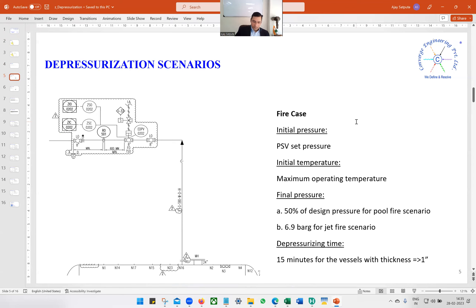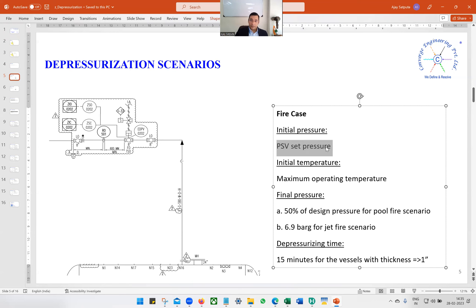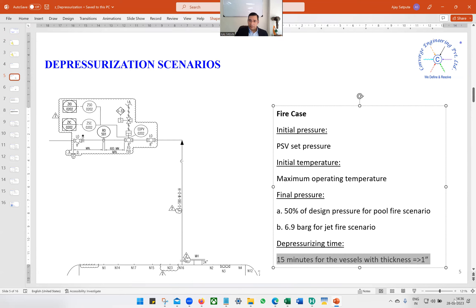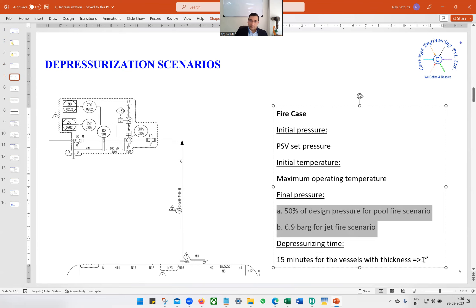There are mainly two scenarios we consider for depressurization. The first is the fire case. The initial pressure is the PSV set pressure, and the initial temperature is the maximum operating temperature. From the PSV set pressure to the final pressure, we want to depressurize within 15 minutes for vessels with one inch or more wall thickness. The final pressure could be 50% of the design pressure for pool fire scenario, or 6.9 bar gauge for jet fire scenario. These guidelines are taken from the ADNOC standard.